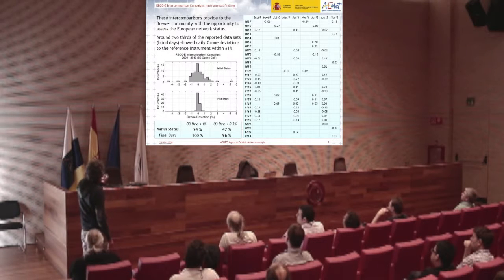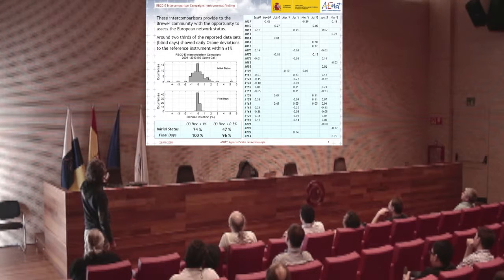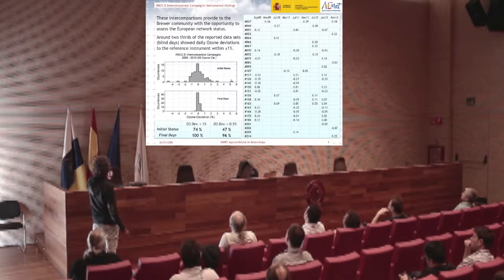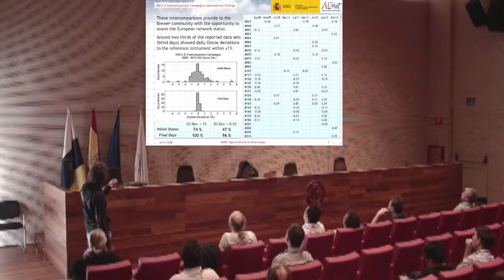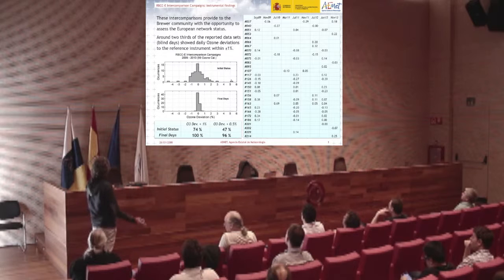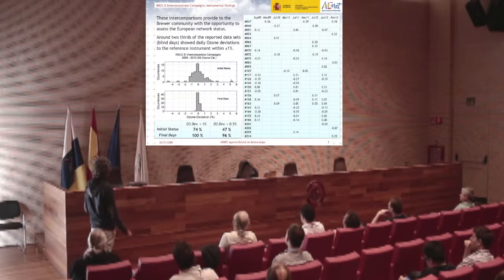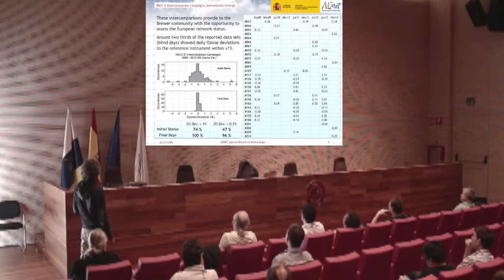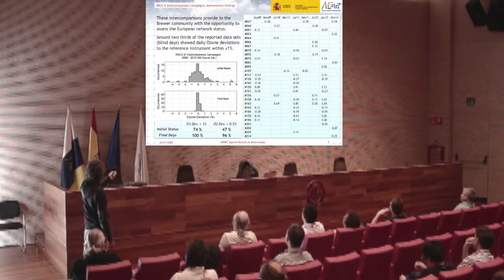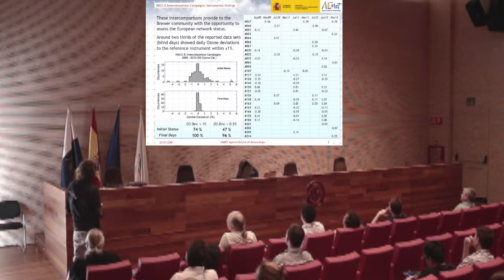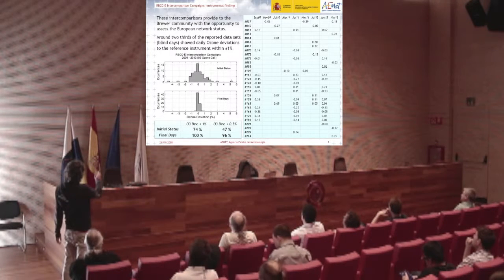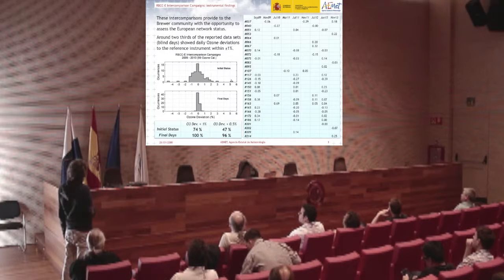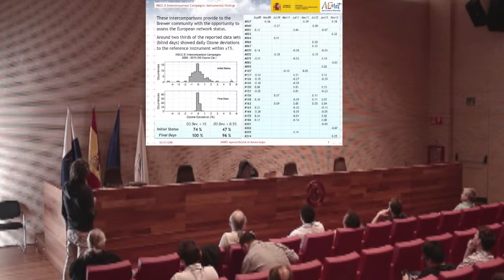Okay, as concerns the blind days, we see that around 2/3 of the instruments were within ±1%, and just around half of the instruments were within 0.5% as compared to the reference instruments. And after the final calibration constants were applied, we get a very good result, a good comparison with the reference standard.